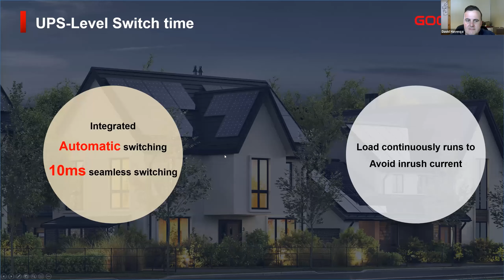So all of our devices have integrated automatic switching, which have 10 milliseconds or less. Some of our newer devices come with 8 millisecond changeover, which is more improved from the previous ones. But as a standard, most of the devices will have that 10 millisecond changeover. So if you have that continuous load running, you don't have loads going off for a few seconds and then back on again. It also helps to mitigate that in-rush current.